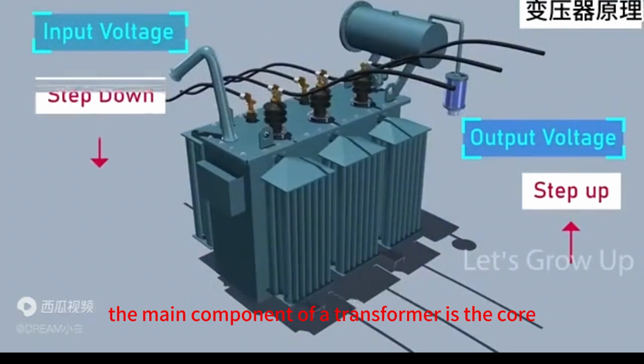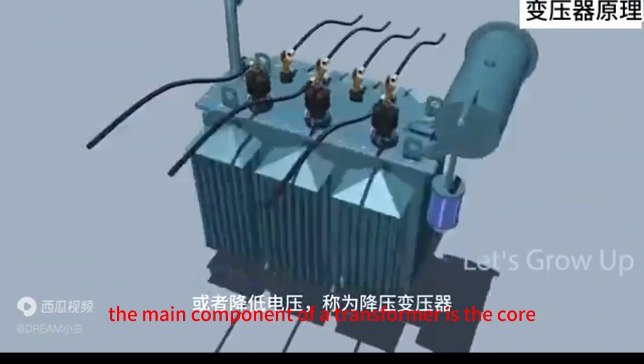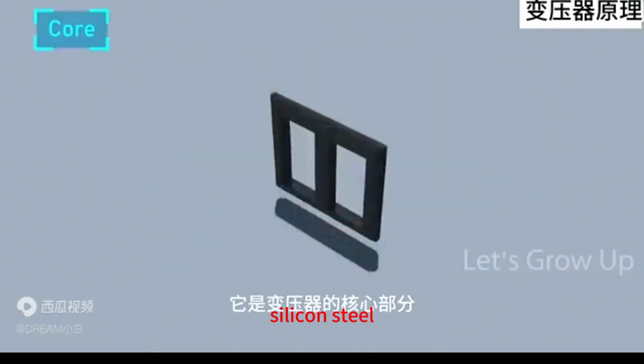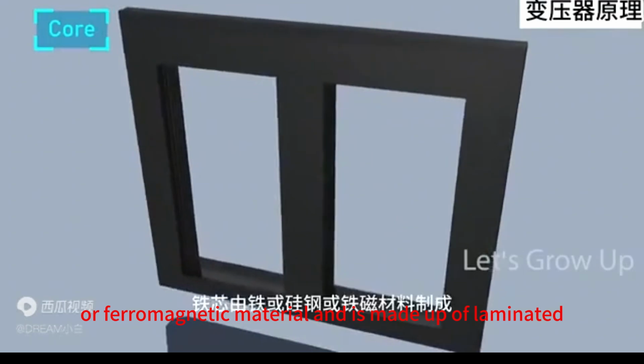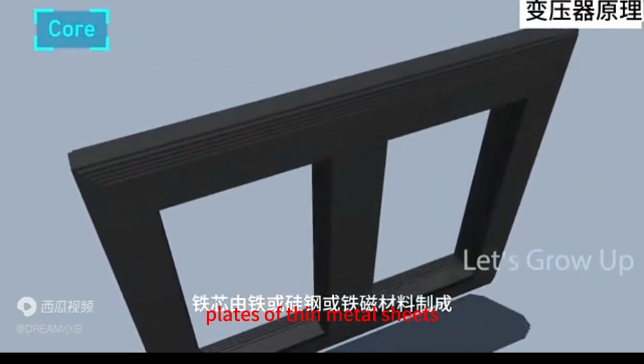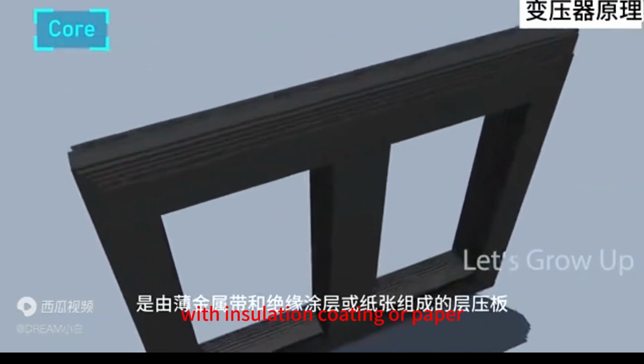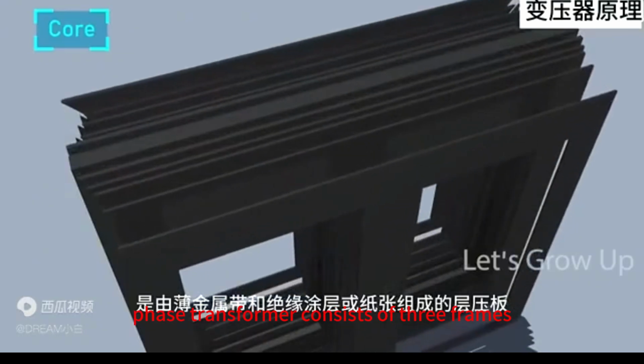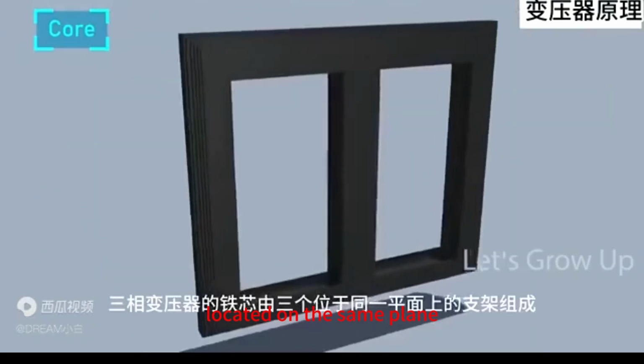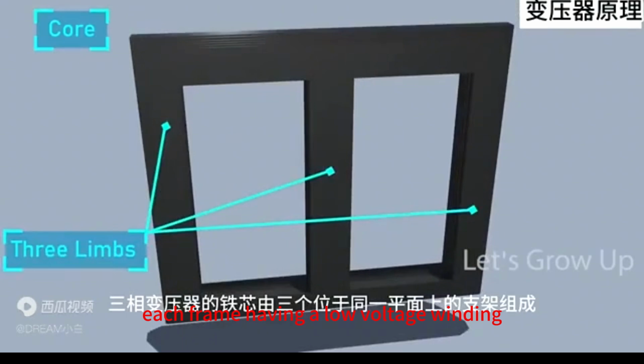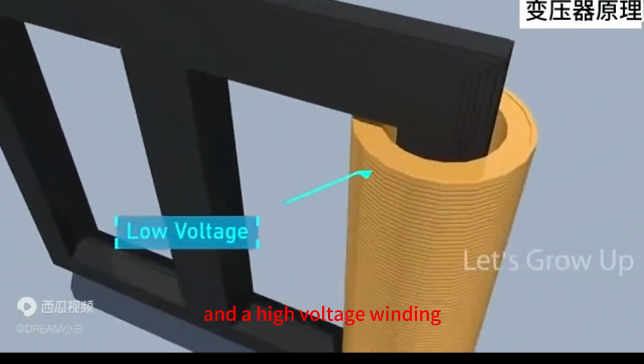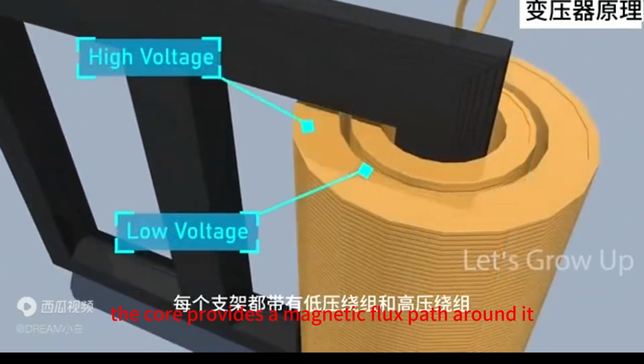step-down transformer. The main component of a transformer is the core, which is the central part of the transformer. The core is made of iron, silicon steel, or ferromagnetic material, and is made up of laminated plates of thin metal sheets with insulation coating or paper. The core of a three-phase transformer consists of 3 frames located on the same plane, each frame having a low-voltage winding and a high-voltage winding. The core provides a magnetic flux path around it.